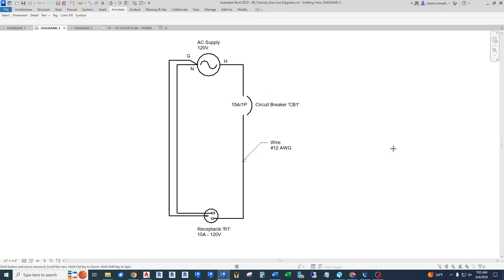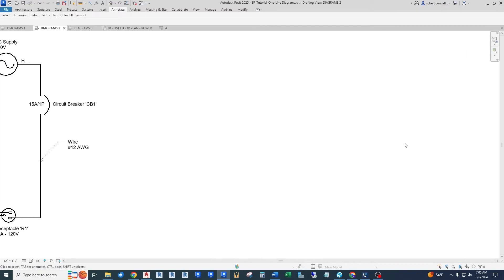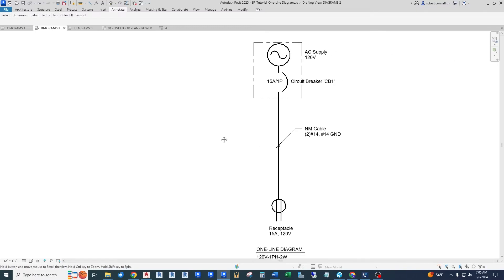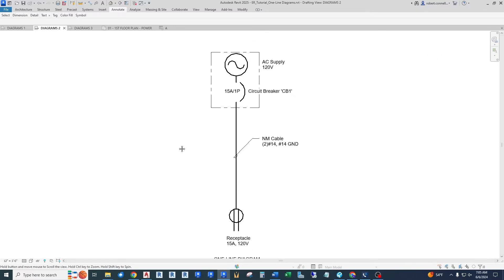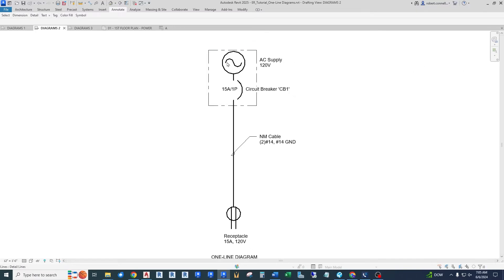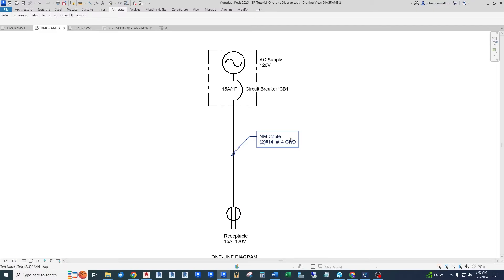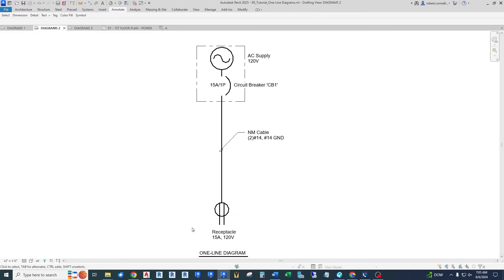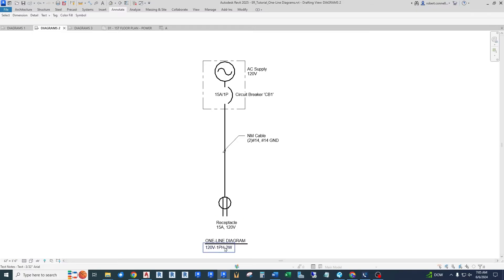Like we did before, let us convert this to a single line representation. There we go. We have a source. We have the circuit breaker, a line simply going down to this receptacle, which represents our load. And then we've called out that this is actually an NM cable, commonly called Romex, with two number 14s and a number 14 ground. So again, this is a one line diagram representation of this 120 volt single phase two wire, we don't count the ground, two wire system. So let's jump into a larger system.